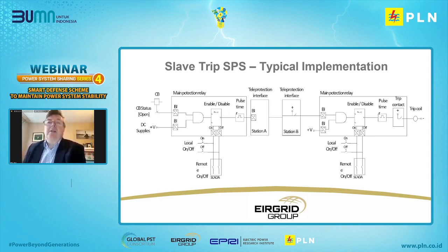Just very quickly how we're doing this: on the left hand side, the circuit breaker status is fed into a binary input on the protection relay. There's also a check to make sure the DC supply is healthy, so they're into an AND condition. Then there's some enable disable logic, so that can be enabled or disabled either locally in the station or remotely from the station or from the system control center. And so if the breaker opens and the DC is healthy and the scheme is enabled, a pulse is sent via the teleprotection to the remote end.